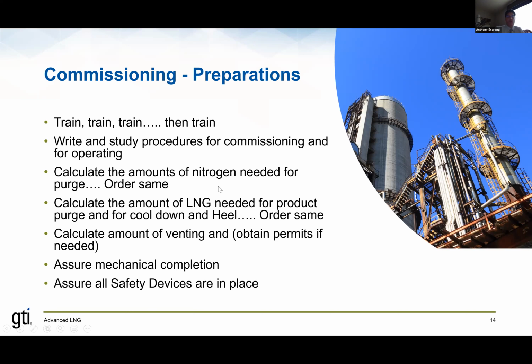Calculate some of the things you need to do for commissioning. You're going to need things like nitrogen, right, to do purging if you're doing it in that manner. Well, you better know how much you need, and you better make sure you have it on site. So you make your calculations and you order the stuff that you need. Calculate the amount of LNG that you need for cool down and for heel in a tank. Sometimes you might want to cool a system down with a cargo of LNG, as opposed to cooling it down with your own LNG that you produce in production. So you might want to calculate how much LNG you have to purchase to do an effective cool down that way, an alternative to producing your own LNG and using it during cool down.